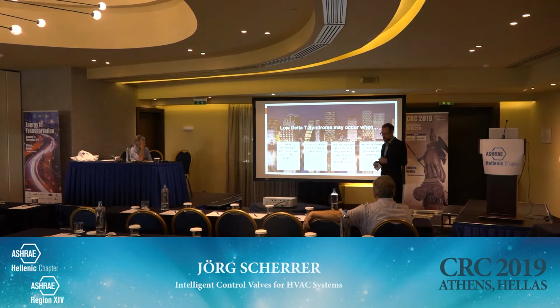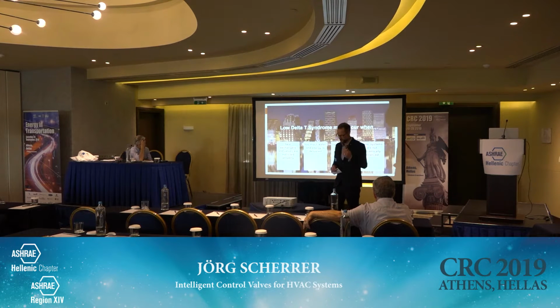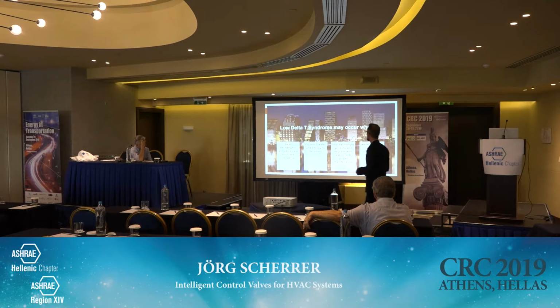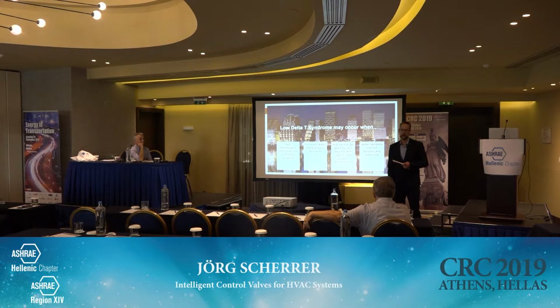The low delta T syndrome has many causes. One is that water systems are not balanced properly. I read a story from Germany that about 80% of the water systems in buildings are not properly balanced. That means I just pump water around and around, and I don't get the right energy. The energy is not delivered at the right time with the correct flow rate.